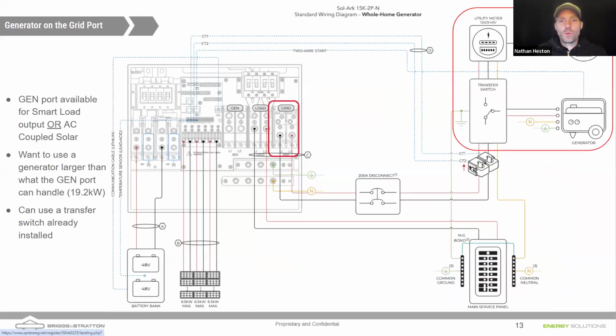We could also use the grid port to bring in a generator. You would do this if you're in an off-grid setting. If you're in an off-grid setting where you don't have a utility connection, Sol-Ark recommends bringing the generator in, if you're going to do one, on the grid port. What does that do, Daniel? Why would we rather have the grid port used for that? It allows more amps. Yeah, you get up to 200 amps of continuous power from the grid port that can pass through to your load center, right?